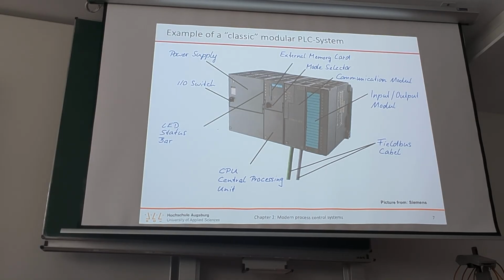And actually, even though they look the same, if you try to use a normal memory card for a long time, you'll find out that it fails after a while. The technology inside the card is different, because they have these long lifetime cycles. The memory card is designed to work for 30 years and not to fail within, I don't know, 5 or 10, because they don't care. So that's why automation systems are sometimes ridiculously expensive compared to the cheap components that you get from IT.